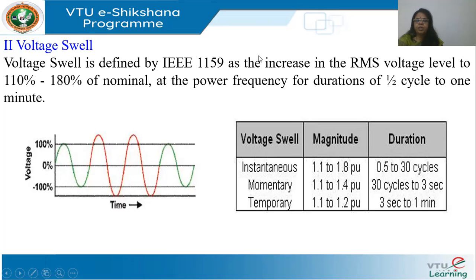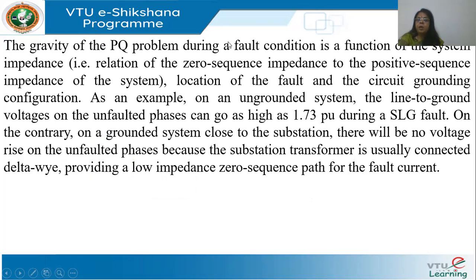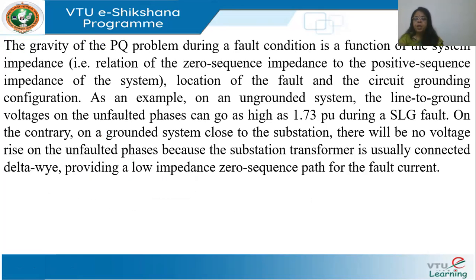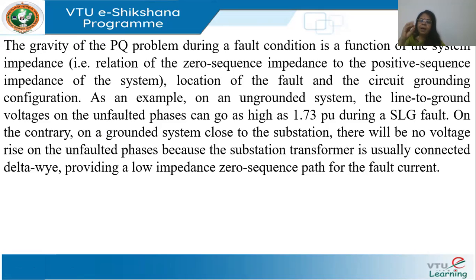The gravity of a power quality problem during a fault is a function of system impedance, zero sequence impedance, fault location, and grounding. In an ungrounded system, a single line-to-ground fault can drive the unfaulted phase voltages as high as 1.73 per unit. EPRI has stated that 80% of power quality problems arise because of improper grounding — proper grounding is one of the most important aspects for improving power quality.